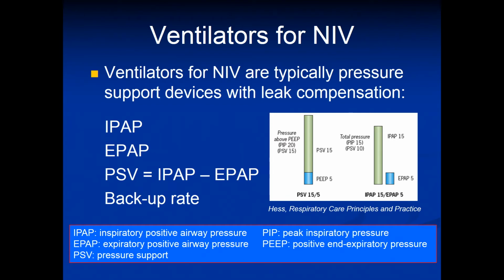This is different than with an ICU ventilator, where the level of pressure support is actually the amount of support that is applied above the level of PEEP. So the IPAP is the peak inspiratory pressure, and with pressure support, the peak inspiratory pressure would be the sum of the pressure support level plus the PEEP setting.